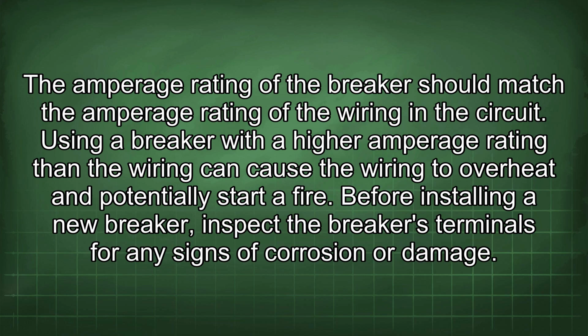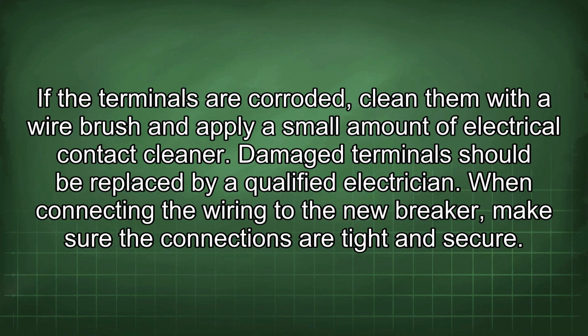Using a breaker with a higher amperage rating than the wiring can cause the wiring to overheat and potentially start a fire. Before installing a new breaker, inspect the breaker's terminals for any signs of corrosion or damage. If the terminals are corroded, clean them with a wire brush and apply a small amount of electrical contact cleaner. Damaged terminals should be replaced by a qualified electrician.